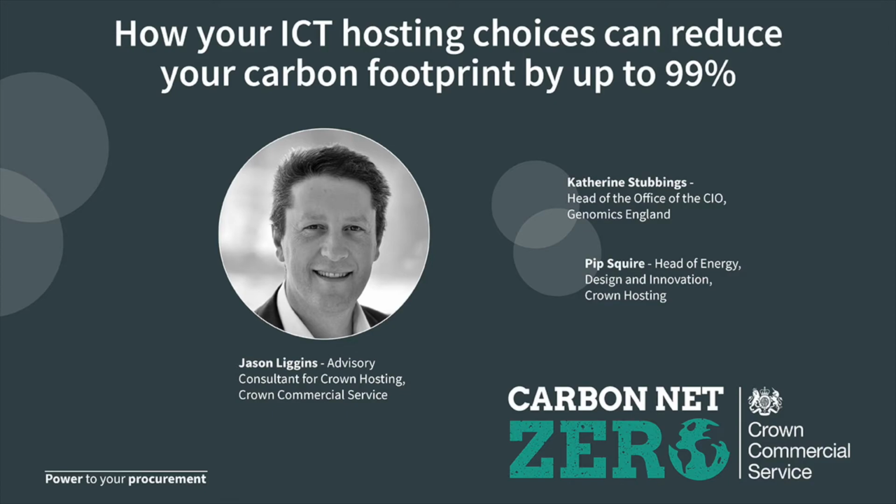A bit of background, Scope 1 carbon is the emissions emitted from self-generation on site. For Ark, this is low. It's less than 150 tons of CO2 per year across our campuses. And it really comes about because we have to run our standby generators for maintenance purposes. Typically, they run for less than 4 hours a year. And by the end of 2022, we'll have improved this because we're replacing all our diesel with HVO, hydrogenated vegetable oil. This will reduce our fossil CO2 emissions by 90%, our particulates by 29%, and NOx emissions by 70%. So that's not just CO2, but we're actually improving the air quality as well.